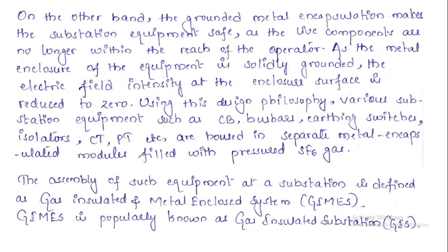The assembly of such equipment at a substation is defined as a gas insulated and metal enclosed system, GIMES. GIMES is popularly known as a gas insulated substation. So the assembly of all these protective devices such as circuit breaker, bus bar, earthing switch, isolator, CT, PT, etc., with the help of pressurized SF6 gas, is known as a gas insulated substation.